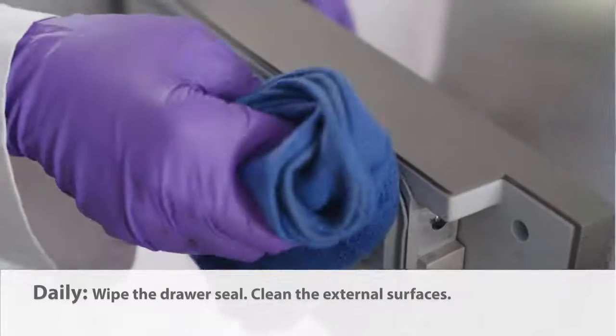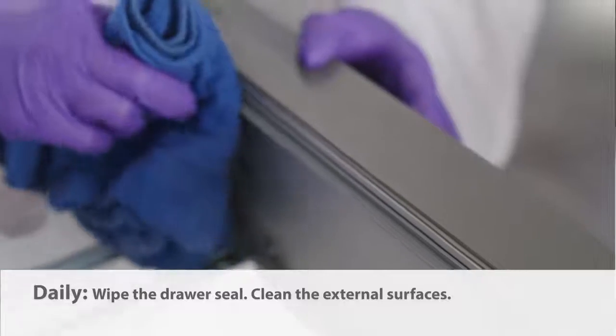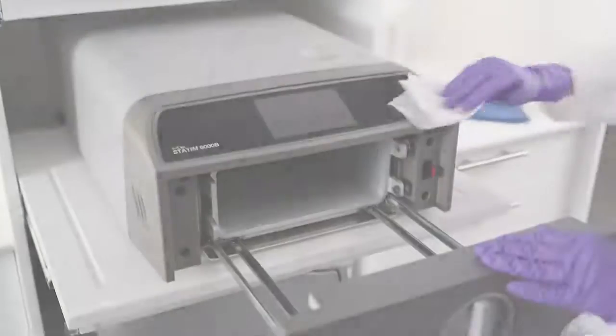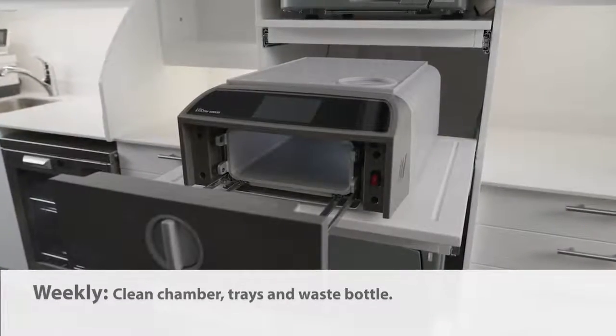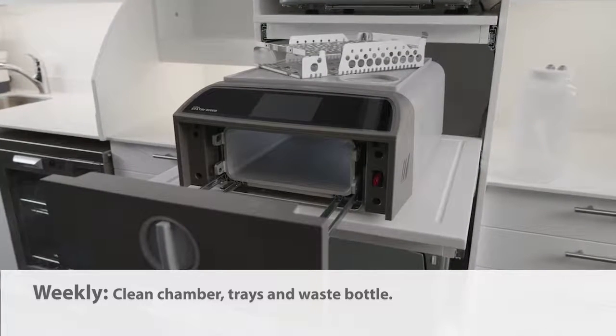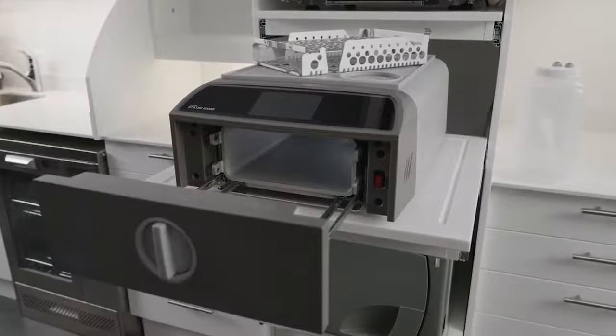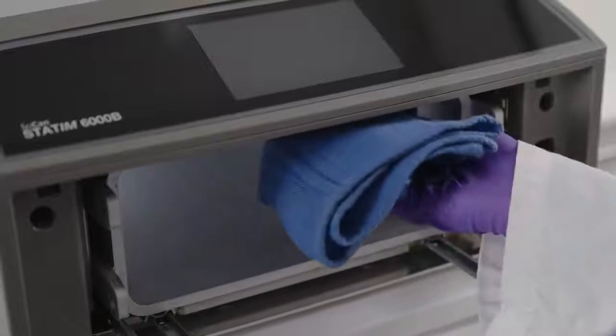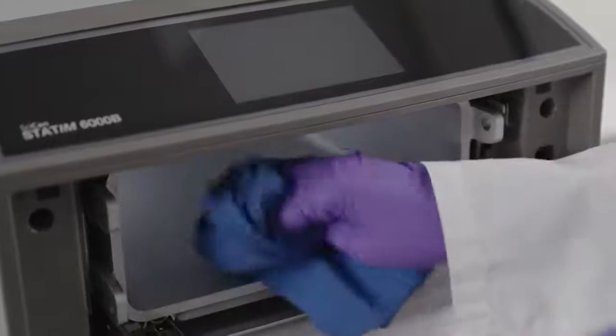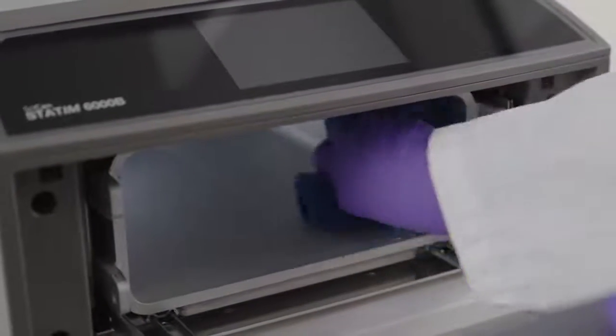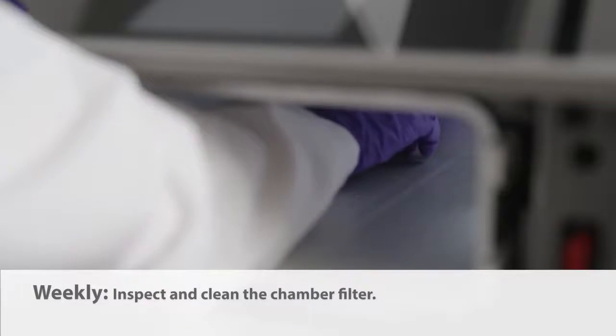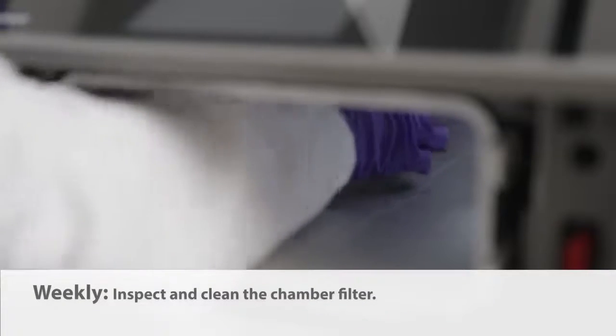External surfaces should be cleaned daily using Optim wipes or a dampened cloth. The sterilization chamber, trays, and if applicable, waste bottles should be cleaned weekly. Clean the chamber and trays using a lint-free cloth dampened with water and wipe them dry. Every week, you should also inspect and clean the chamber filter.